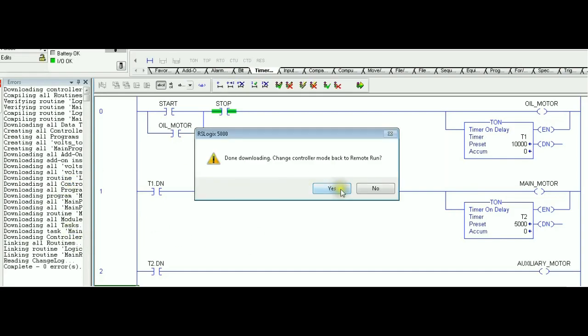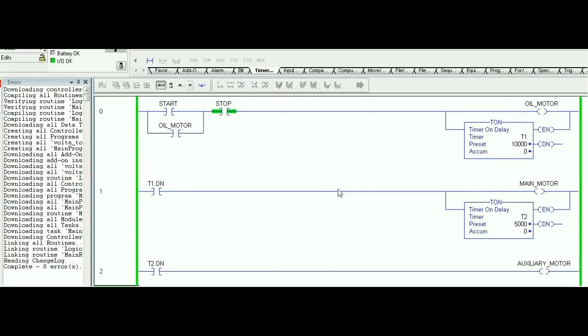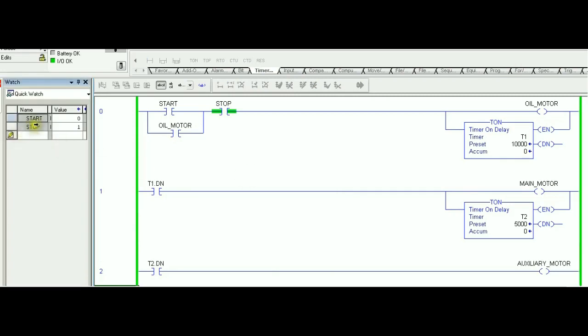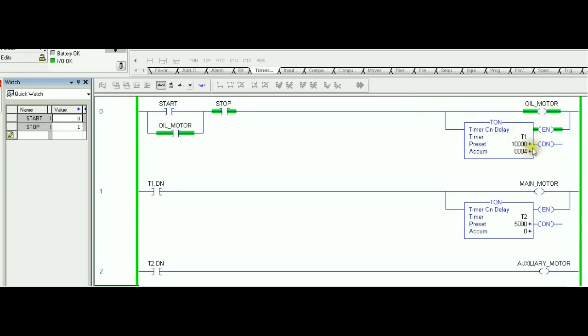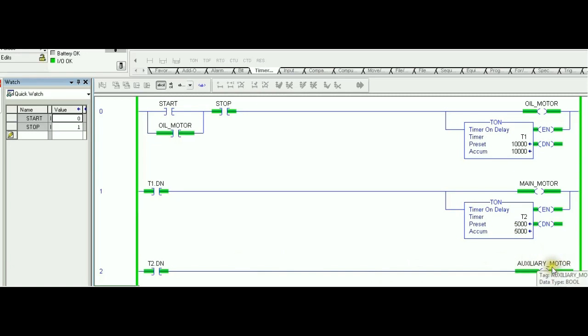So, no errors. That's a good thing. Let's show right now the start is normally open. That's what you can see to the left side of the screen. It's reading zero to the PLC memory. You press that switch. It changes to one. Even when you let go, the latching take care of maintaining the path. So, oil motor is on. Timer is on for 10 seconds. 10 seconds later, the done bit is set. The main motor is on. Second timer is on for five seconds. This guy is on. The auxiliary is five seconds after this one. And main motor is 10 seconds after oil motor.